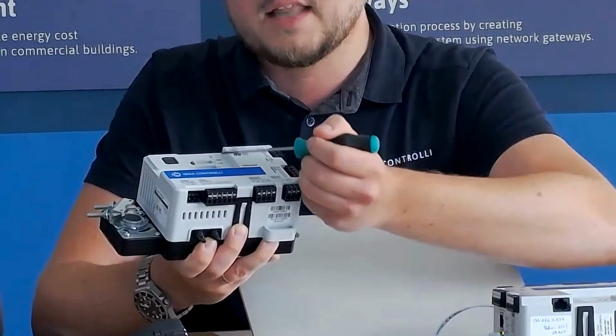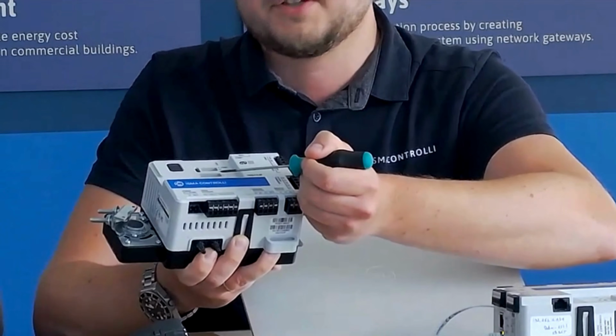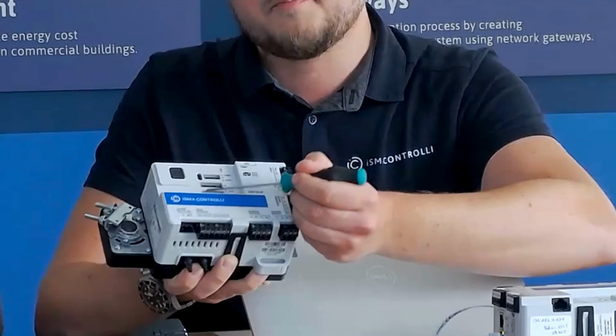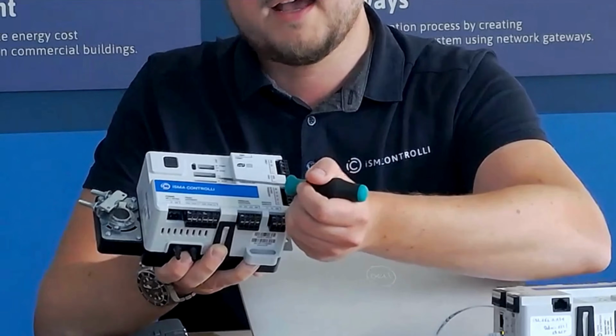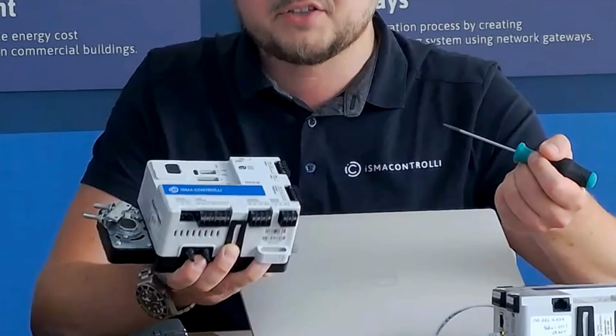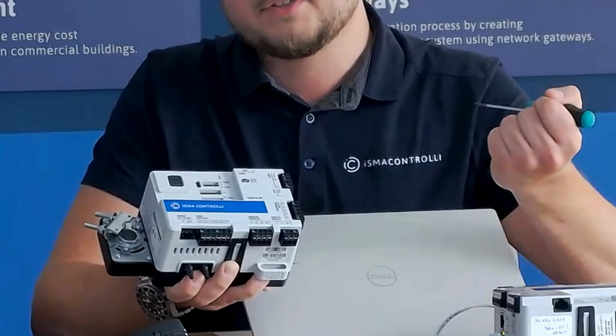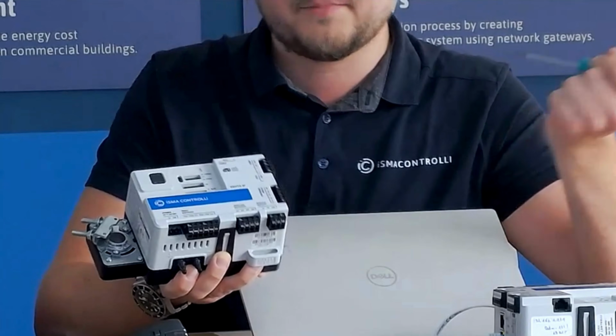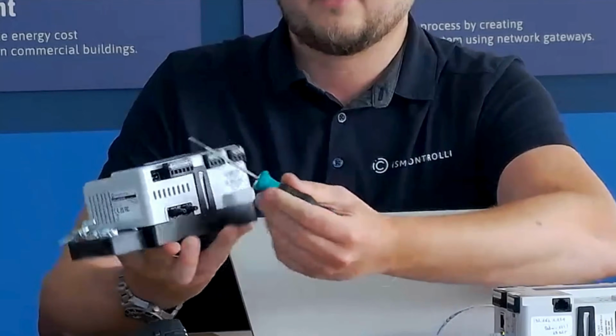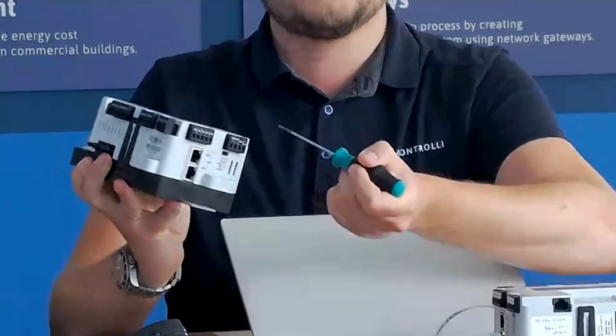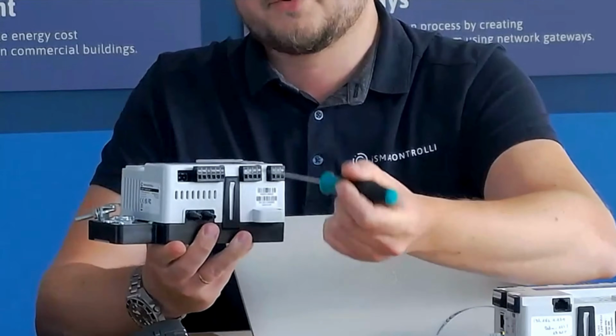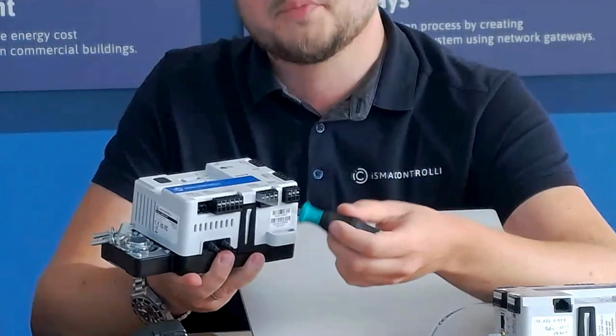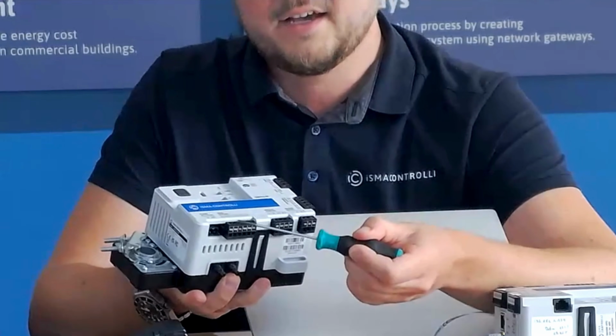But if you would like to simply configure the application as it is, you can set the first bit of dip switch number 3 and do the initial configuration as Tomasz described, just from the controller itself. We have 13 inputs and outputs that go around this controller, and of course the power itself. The controller is powered from 24-volt AC or 24-volt DC.